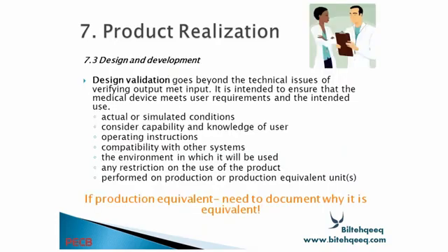And design validation goes beyond the technical issue of verifying output met input. It is intended to ensure that the medical devices meet user requirements and the intended use.